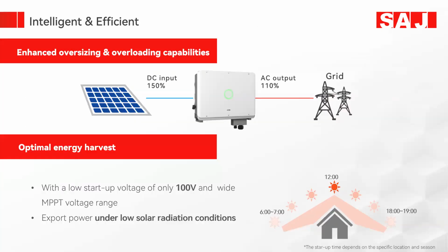Intelligent and efficient enhanced oversizing and overloading capabilities. DC input is 150%. If you have a 10 kilowatt inverter, you can install 15 kilowatt PV panels with that inverter, and AC output is 110%. Just like if you have a 10 kilowatt inverter, you can get AC output up to 11 kilowatt.